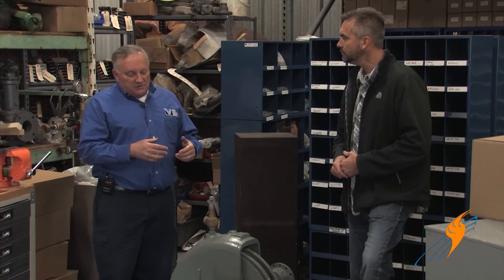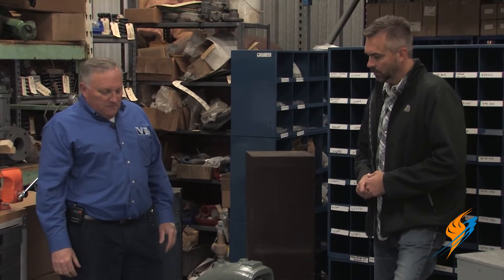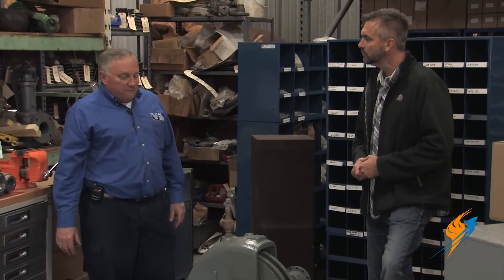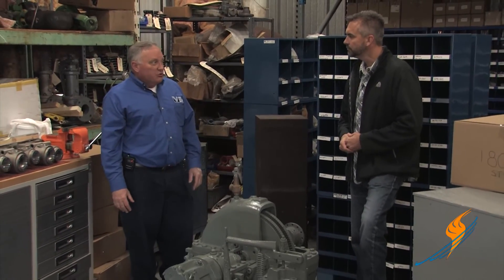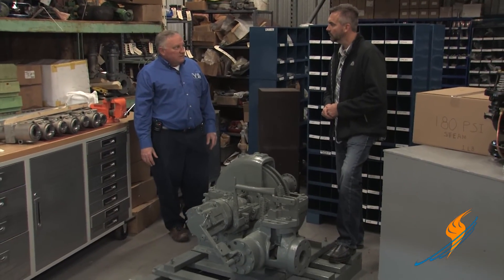In large part, if you're using a generator, the payback is largely dependent on what you're paying for electric. It's going to be much quicker if you're paying 12 cents per kilowatt hour as opposed to 6 cents. These are fairly simple devices — they've been around since the 1920s, the designs are mature, and there's really not much more efficiency to be gotten out of them. They're a tried and true product, and you can get 30 to 40 years out of one of these.